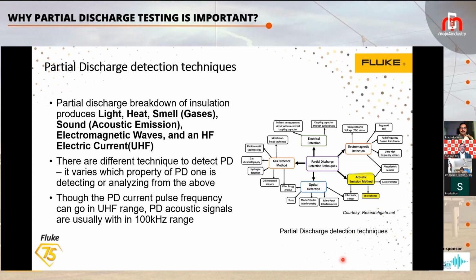And when it comes to partial discharge detection, as I said, when partial discharge breakdown occurs in installations, it will give outputs like light, heat, smell or gases, and sound, apart from electromagnetic waves. That means you can detect the partial discharge using various techniques, either through light, through heat, through acoustic emissions, or through electromagnetic emissions.